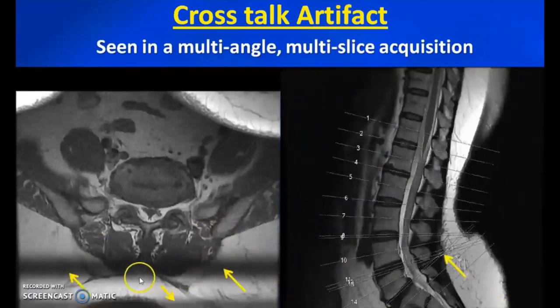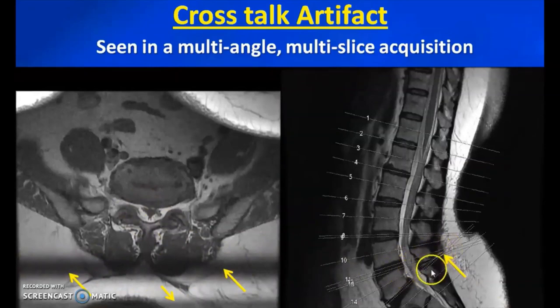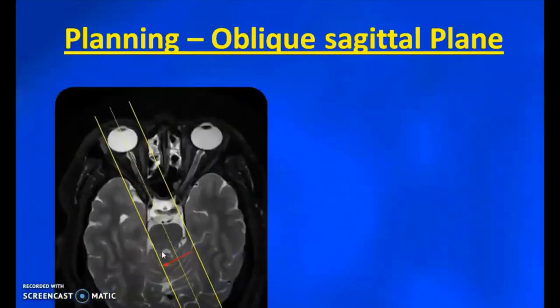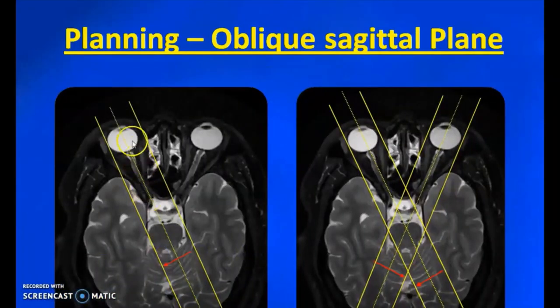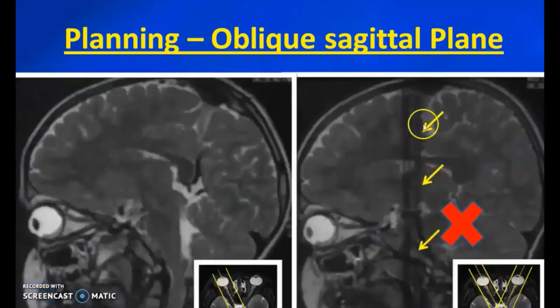Another common artifact is the cross-talk artifact seen in multi-angle and multi-slice acquisition. These artifacts appear as black bands seen opposed to the spinal cord where the axial sections overlap one another. To remedy this, reduce the angulation or separately plan for those particular slices to get an artifact-free image. This cross-talk artifact also happens in oblique planning of the orbit — if you plan both orbits in a single sequence, you will get this type of artifact.